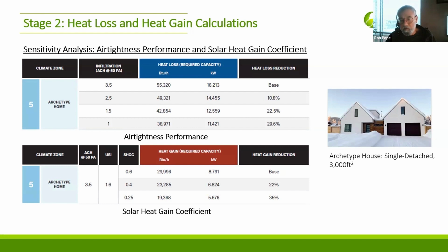We'll go down to 0.25 on the glass. But if you want to stay above where you start to see that tint, you want to be in a 0.3 range or a little higher. We find the sweet spot to be about 0.32, 0.33 in that ballpark. And we also find that any manufacturer of windows is able to provide that.